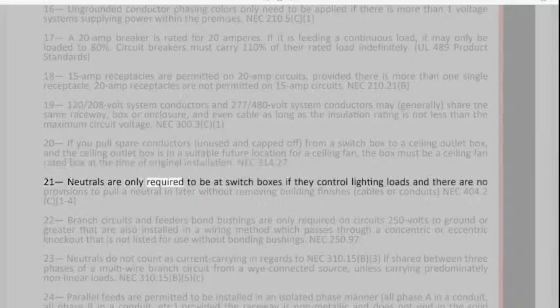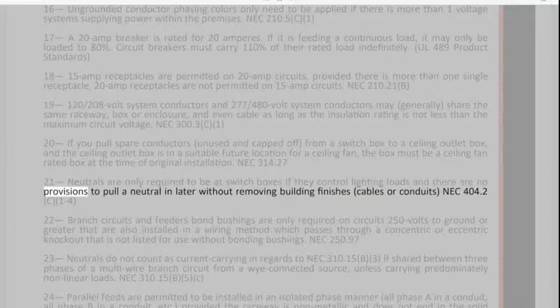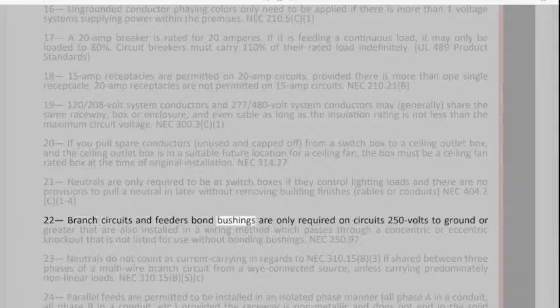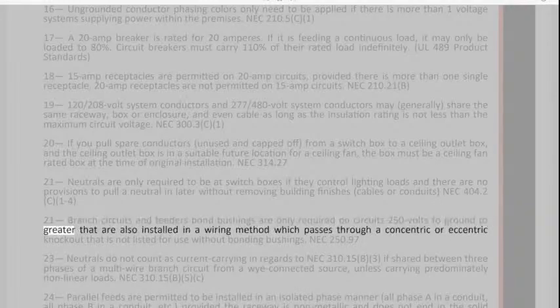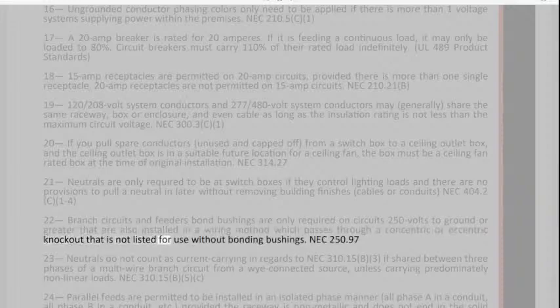21. Neutrals are only required to be at switch boxes if they control lighting loads, and there are no provisions to pull a neutral in later without removing building finishes, cables, or conduits. NEC 404.2C 1-4. 22. Branch circuits and feeders: bond bushings are only required on circuits 250 volts to ground or greater that are also installed in a wiring method which passes through a concentric or eccentric knockout that is not listed for use without bonding bushings.